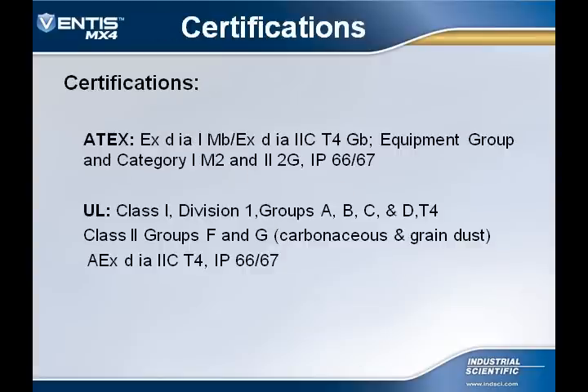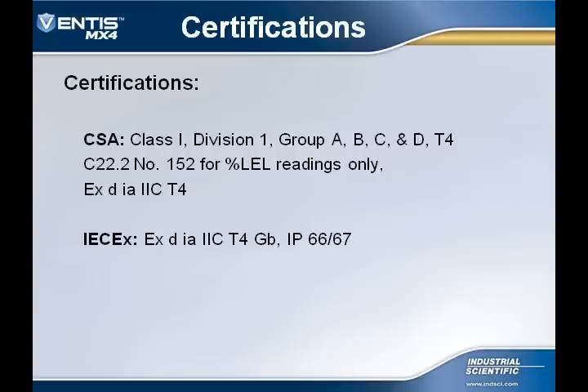The Ventis MX4 is classified as being intrinsically safe. This means that the instrument will not act as an ignition source in the event of an internal failure. The agencies that have certified these classifications are ATEX and UL, CSA and IEC. The Ventis has also achieved an ingress protection rating of IP67 from UL, with other approvals pending.